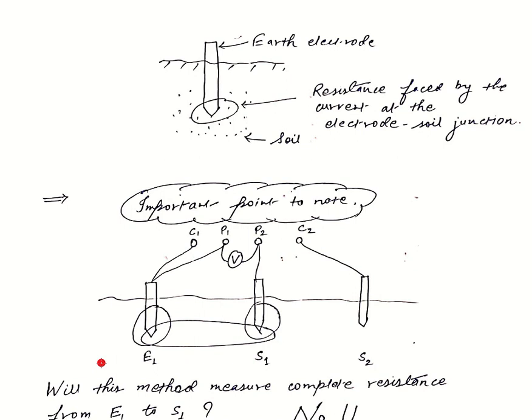The answer is no. As we can see here, there are three regions in total: this region, this complete region, and this region. We want resistance of this region only as earth resistance, because this is our main earth electrode and these are just spikes which we have connected for measurement purpose.